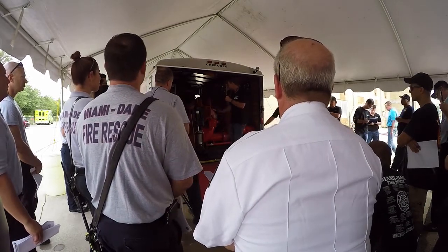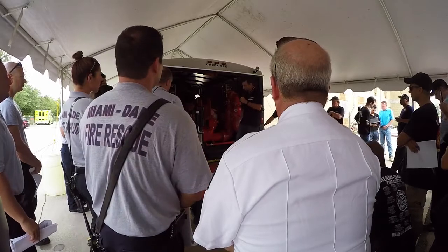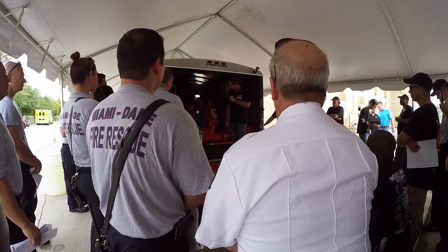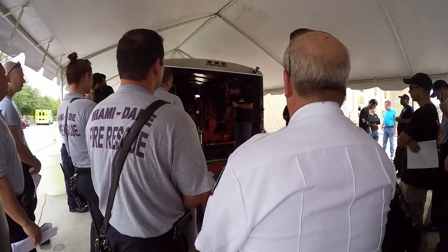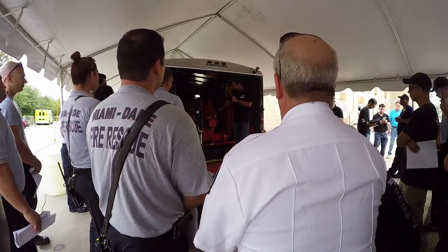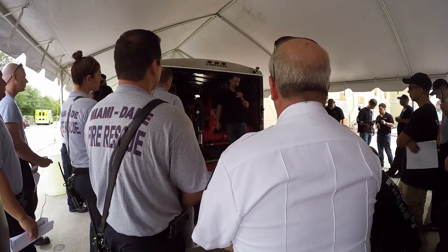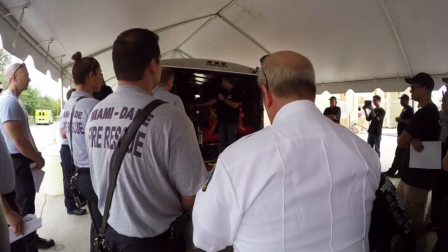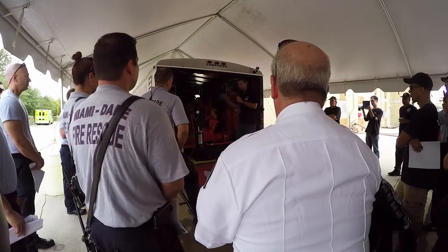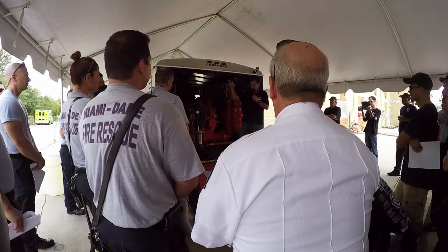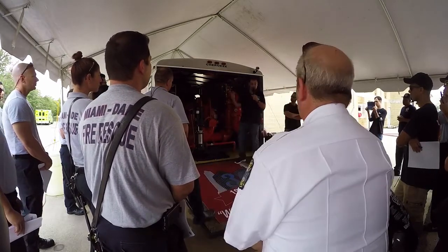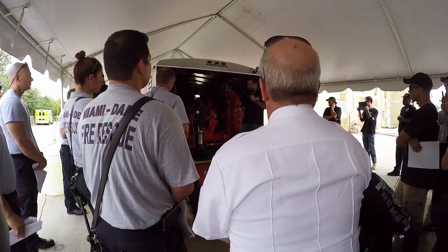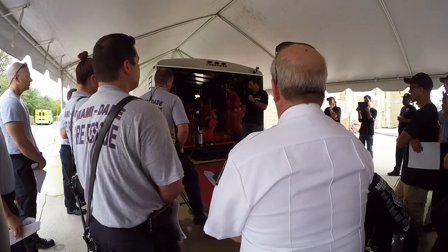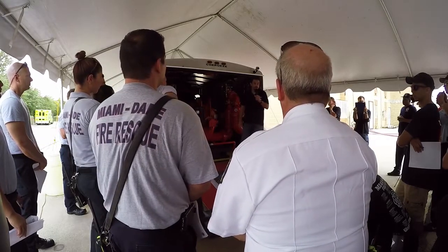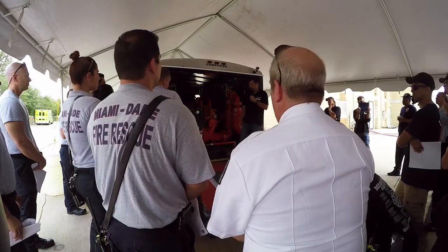So this is the jockey pump, this is the fire pump, this is a horizontal split casing fire pump, which means the casing is split horizontally to the shaft. This pump is driven by a diesel engine. You may see these electric, you may see them standing up, you may see the motor on the top, the pump on the bottom, you may see the one you have out front, vertical turbine. There's probably more steam turbine, you know, there's probably a bunch of different fire pumps you would see.